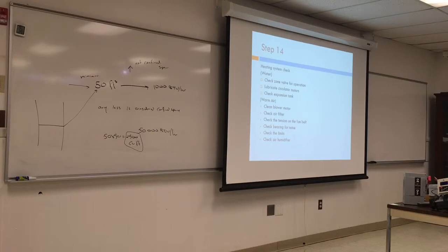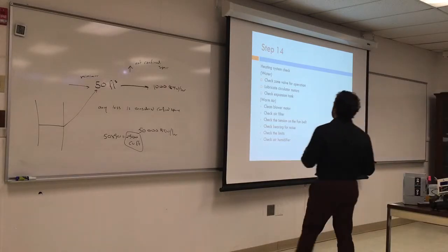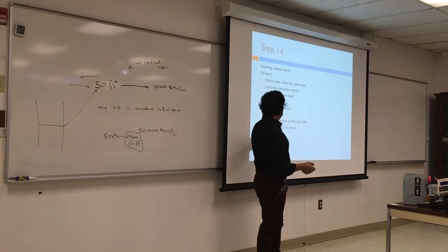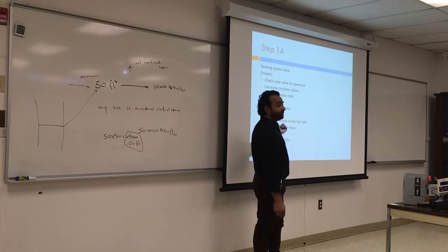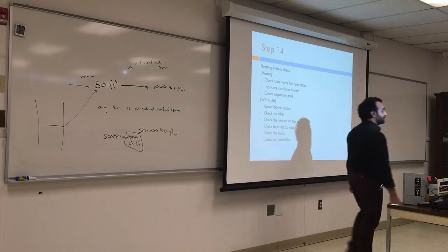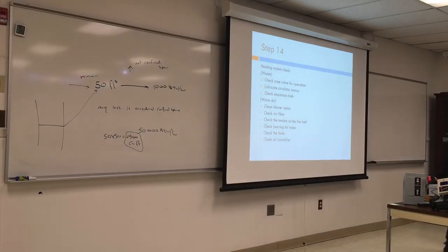So you're gonna go with the water to heat, we did that with the hot water system, the HB Smith. Make sure the pump is running between the limits, make sure it's producing heat. If it's warm air, clean the blower motor, check the air filter. Air filter should be changed semi-annually. Check for the tension in the fan belt, if there's a fan belt. Check the bearing for noise. It should not be too noisy. It should be just humming, but not noisy.